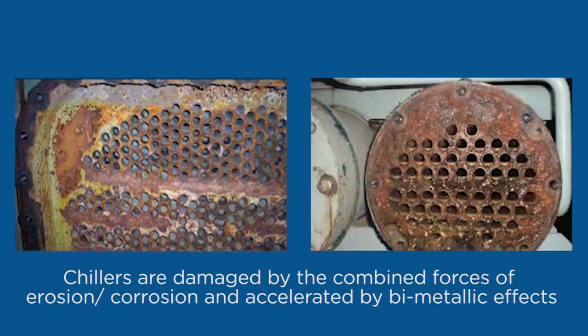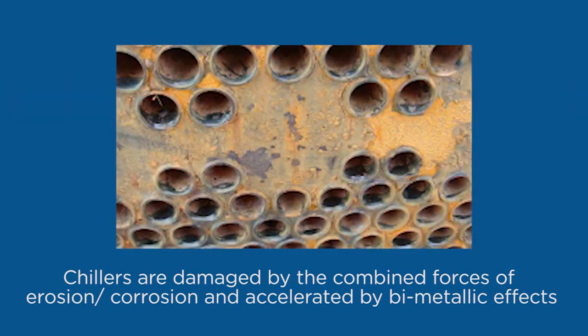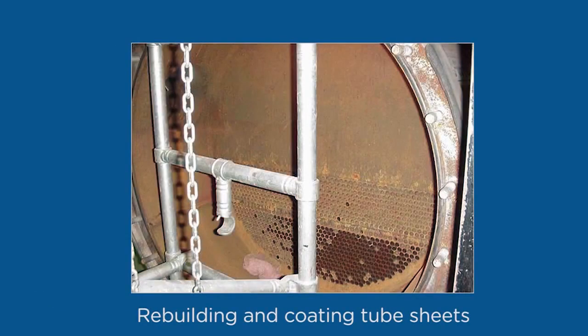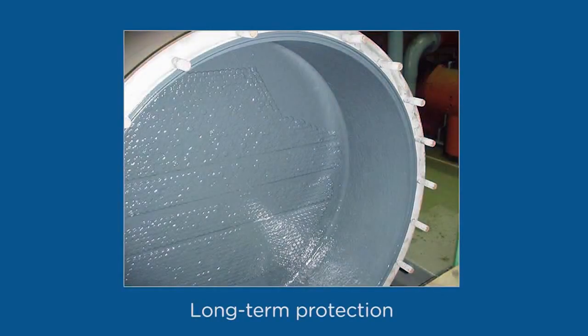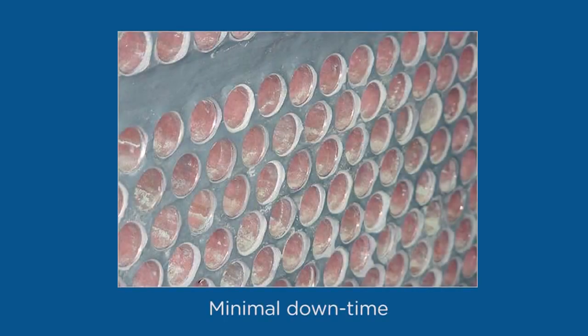During annual inspection and servicing, the end covers on chillers should be removed for general inspection and testing for leaks. This is an excellent time to undertake a Belzona protective coating system. For decades, major manufacturers of chillers like Trane, Carrier, and York have been rebuilding and coating tube sheets with Belzona. More and more of these major manufacturers' customers want the long-term protection and minimal downtime afforded with Belzona and specify our polymers for their equipment.